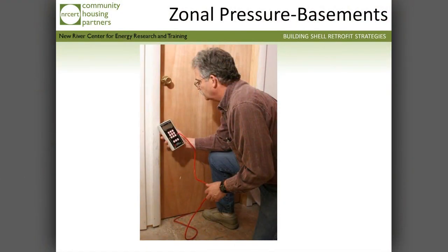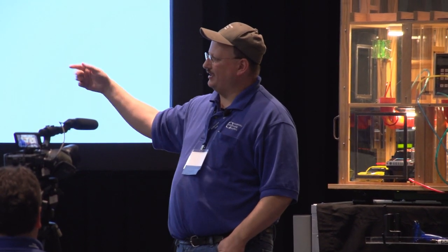Right, you're trying to get the hose in there. In the real world, that's the way it's operating right now. But you know that's one of the leaks, because that's the gap. You're probably going to weather strip that or seal it, but let's see how much difference it makes. Sometimes we'll use duct mask, a temporary tape. They have all kinds of different brands of that. I've even taped the whole door jamb just to see what happens. But you want to try to get the probe in there. Sometimes it'll curl around on you and come back if you're not careful.